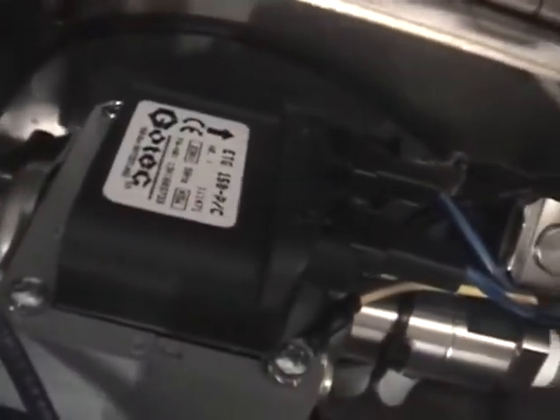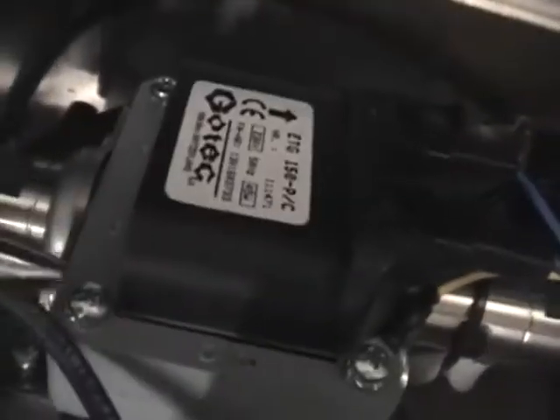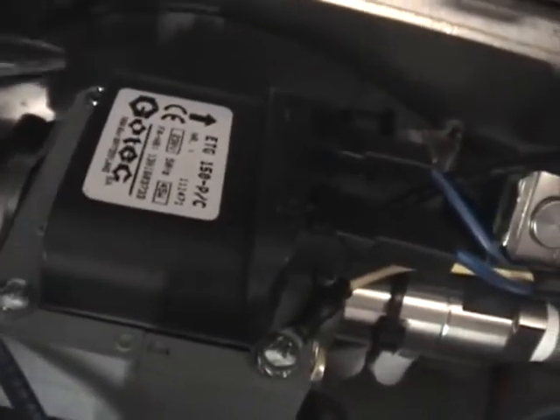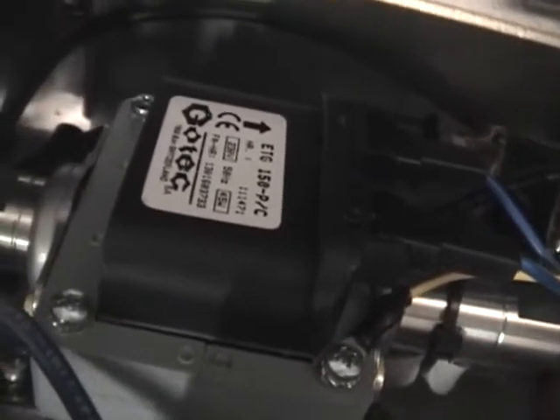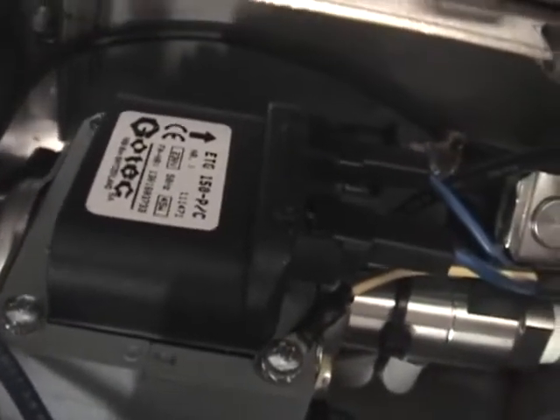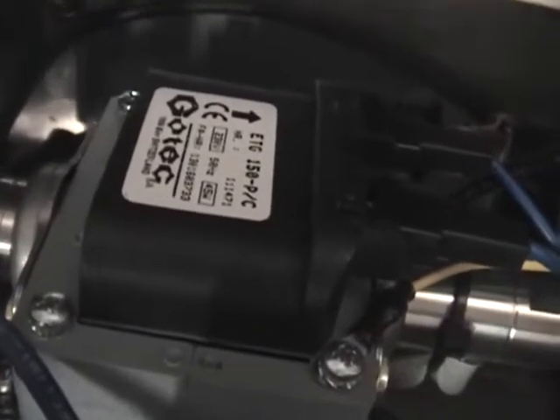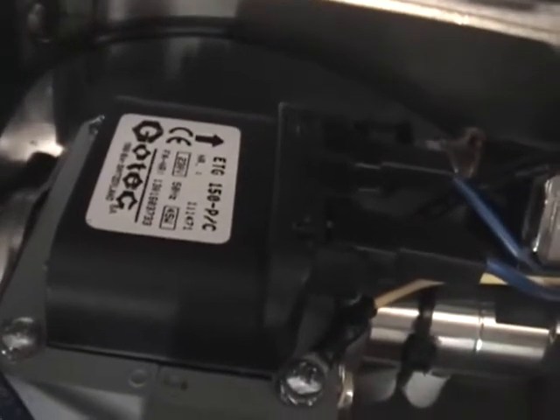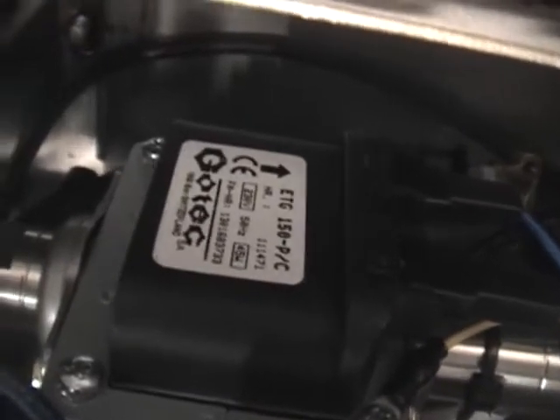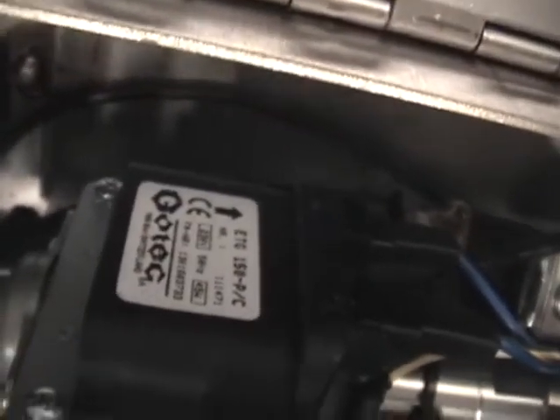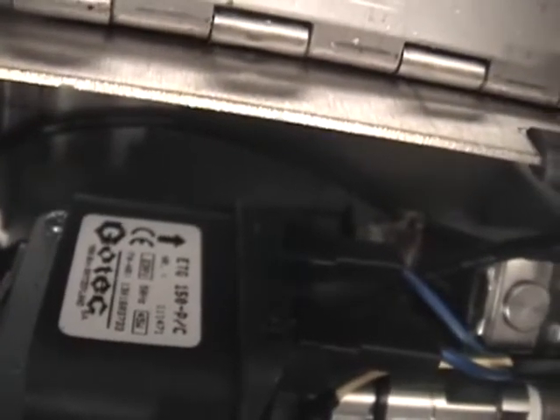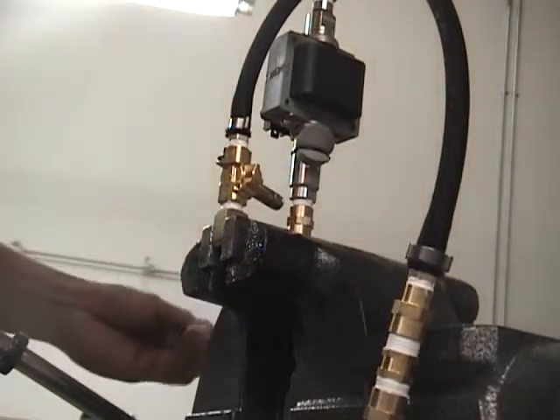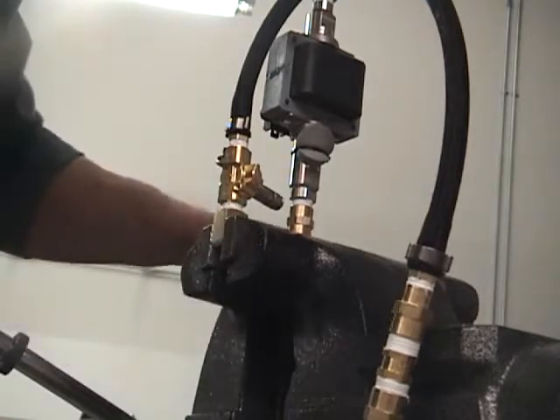There are 4 screws that hold the pump itself. There's 2 towards the top, and then there's 2 towards the bottom. You need a small Phillips screwdriver. Once you take the first 2 top screws off, then since you removed the bolts on the bottom, you'll be able to lift up the plate to get enough room to get the 2 bottom screws that are holding on to the pump. Once the pump assembly is out, you can use a vise to make it easier to take it off.